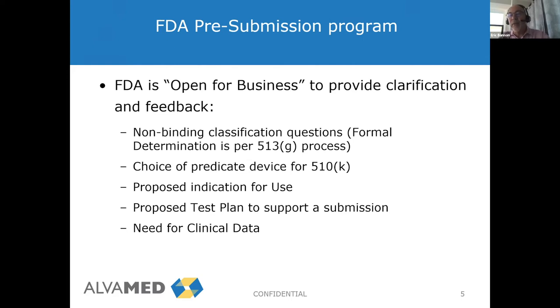It's background on the device, information around what you propose for the testing, and most important, it lists up to 5 questions you want the FDA to provide feedback on. Those are the questions you want answered so you understand what to do for a future submission. Things you can cover: choice of predicate devices for a 510K, indication for use, intended use - an important one, making sure you fit into the population you want to use your device for, proposed test plan, the need for clinical data.